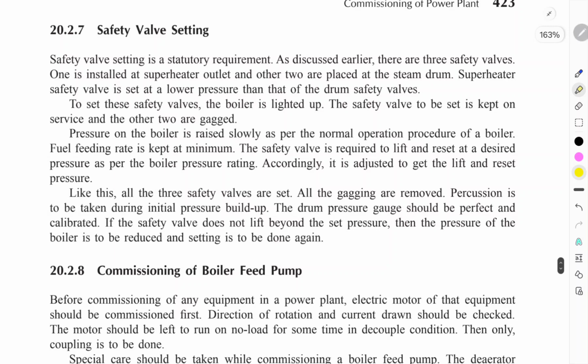So, safety valve setting is the new topic. How to do the safety valve setting? Safety valve setting is a statutory, compulsory requirement. As discussed earlier for the boiler, there are three safety valves. One is installed in the superheater outlet and the other two are placed on the steam drum. The superheater safety valve is set at a lower pressure than the drum safety valve.